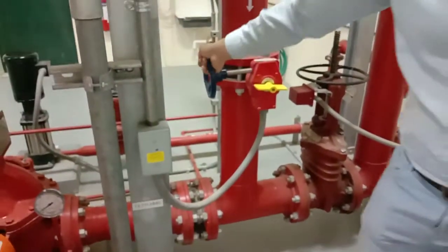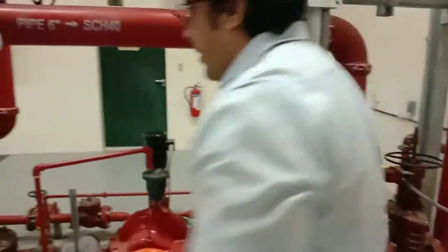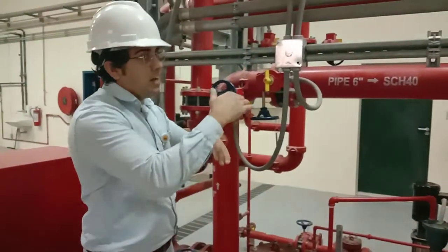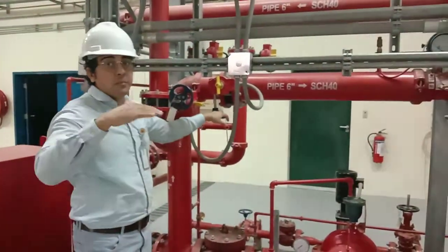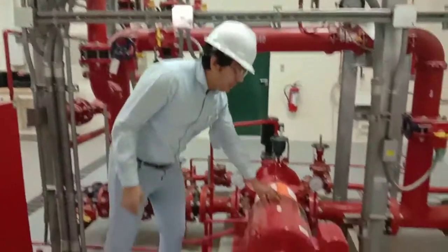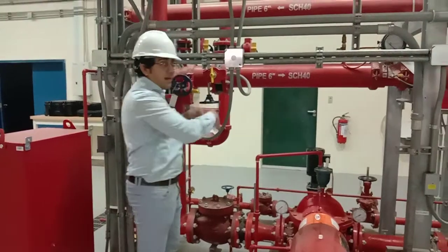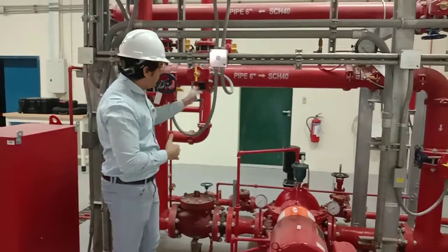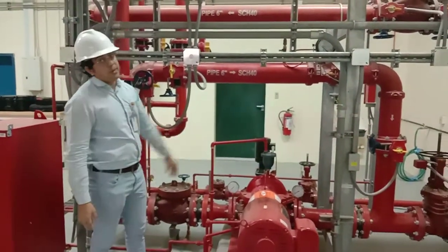Here we can control this valve. We can open it fully, or we can open it partially, not exactly here, we have to open here. It is partially. First open this half, and then a little bit more than that. At the first opening, we will measure the 100% rating. So your pump is at 500 GPM at some pressure. We have to note that one. And further, we'll go on and increase the size so more volume of water will go outside. At that time, we will measure for 150% of the rating at the 65% condition.